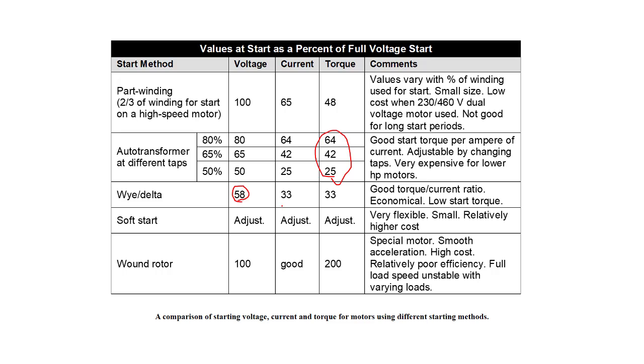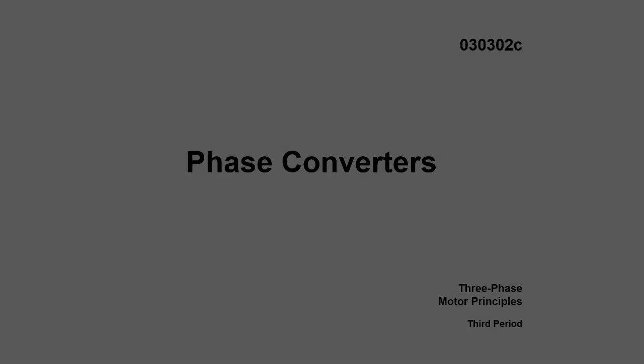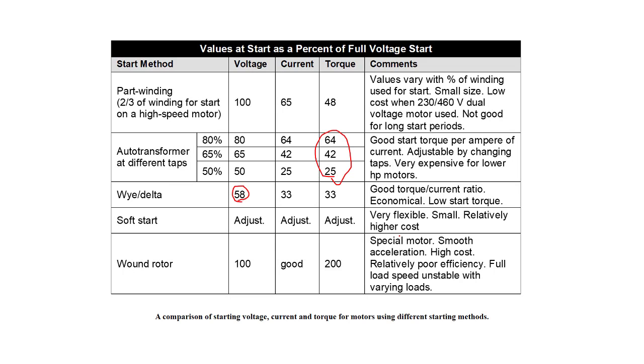Wound rotors with adjustable starters are very good. High torque, and we get some speed adjustment with them. Current is good, but they're big, bulky, and they require a lot of maintenance. So that's about all I'm going to have to say about reduced voltage starters for now.